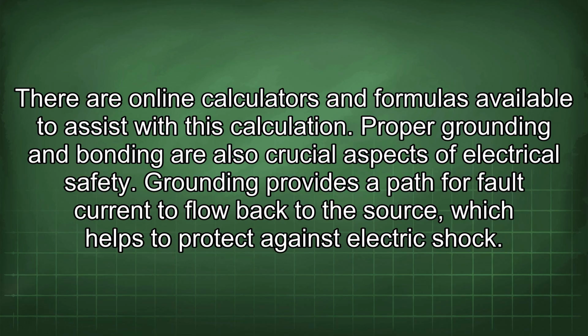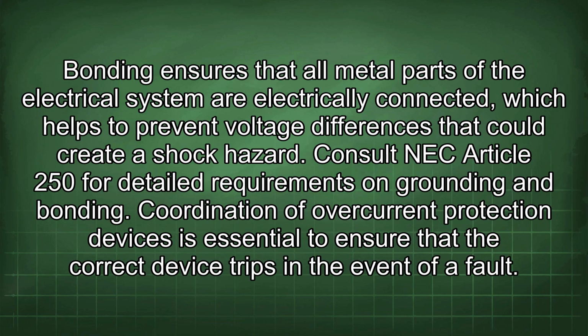Proper grounding and bonding are also crucial aspects of electrical safety. Grounding provides a path for fault current to flow back to the source, which helps to protect against electric shock. Bonding ensures that all metal parts of the electrical system are electrically connected, which helps to prevent voltage differences that could create a shock hazard. Consult NEC Article 250 for detailed requirements on grounding and bonding.